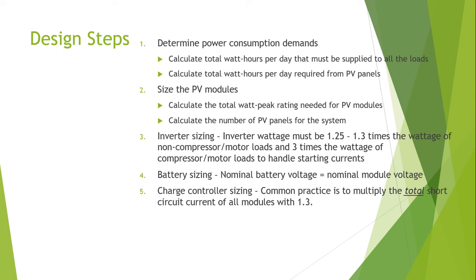In the fifth step, we calculate the charge controller sizing. The common practice is to multiply the total short-circuit current of all the modules by 1.3, so that the charge controller sizing is 1.3 times the actual requirement.